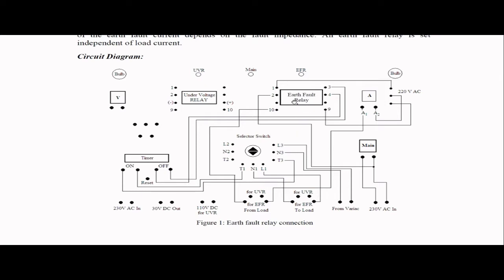Now here you see that this relay, this ammeter and the load are connected in series. A variac is required to give the variable voltage here. As a load, here we use a transformer. You know the transformer has two sides: one is the low voltage side and one is the high voltage side. As the power is constant on the low voltage and high voltage sides of the transformer, the voltage-current multiplication remains the same. So in the low voltage side, we connect it in series with the relay coil, and in the high voltage side, we connect it to the variac. That means if I increase the voltage in the high voltage side, then similarly the low voltage side current will also increase, and this current will be treated as the fault current, because in every experiment on the relay, we need to create an artificial fault.